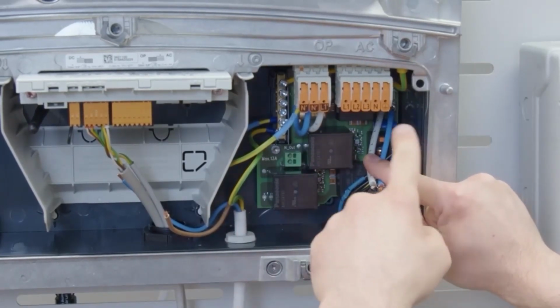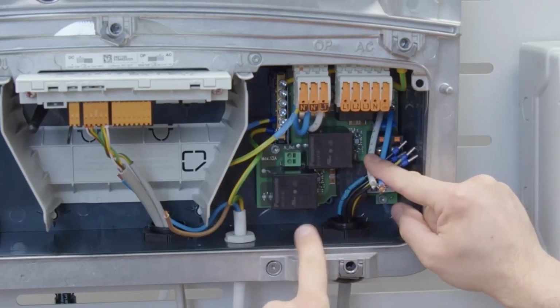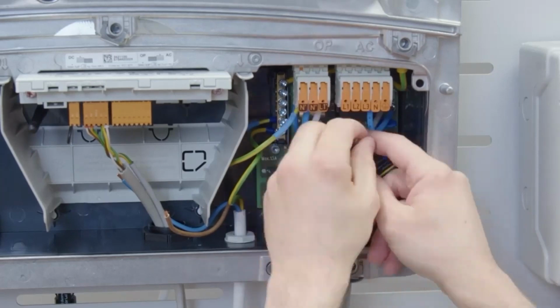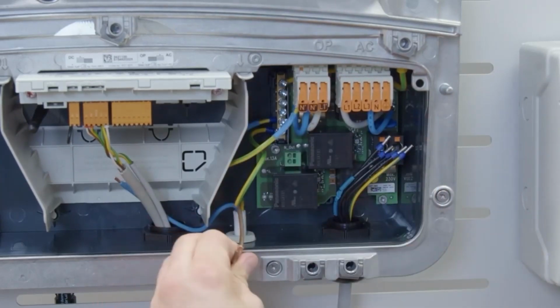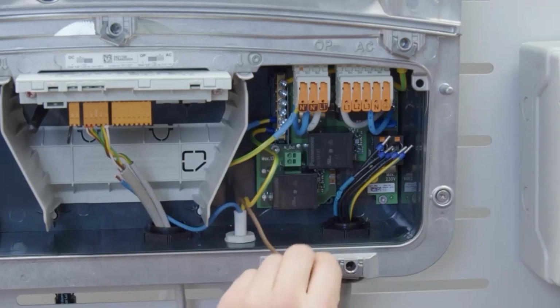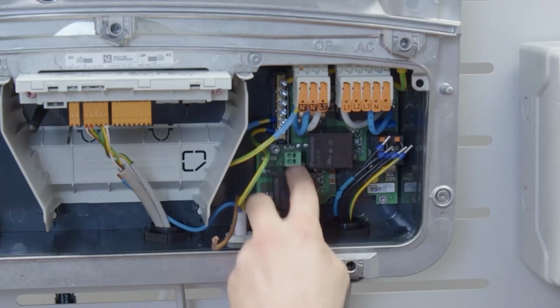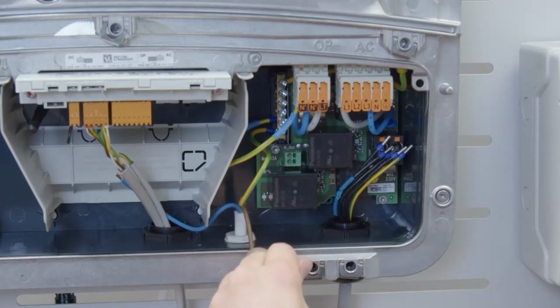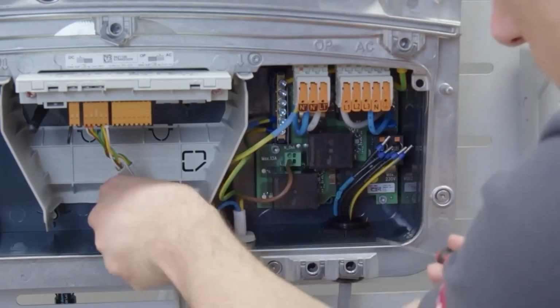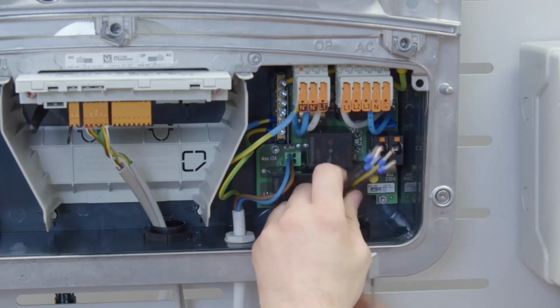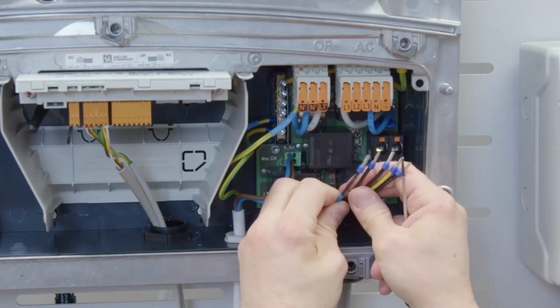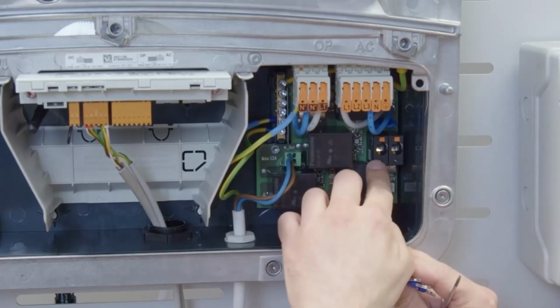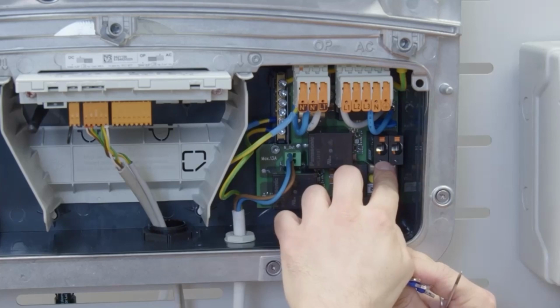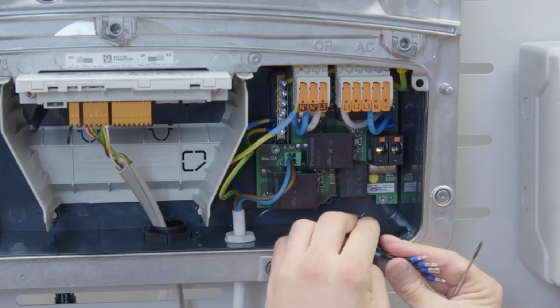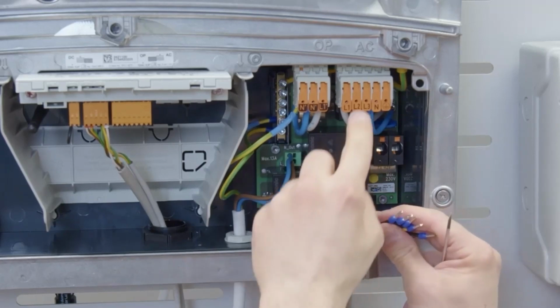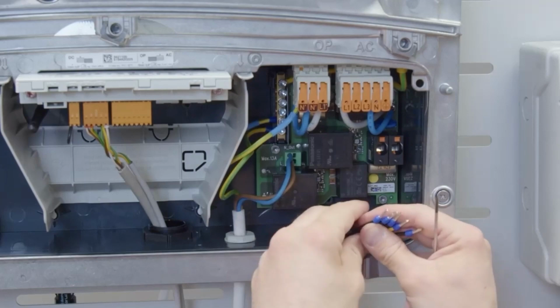Next, we do the connection between the PV point comfort card and the connection point to the inverter. As soon as you finish, you can now connect the PV point load directly to the PC board with the screws that you find down below here. There is a cable clamp and you can use that to install your electric socket, for example. Last but not least, we want to install the AC connection part from the electrical grid to the inverter. And therefore we have one last clamp on the right bottom side of the PV point comfort, and we want to install phase 1 and the neutral conductor to make sure that the PV point comfort is continuously supplied. Phase 2 and 3 can be directly connected to the inverter clamp.